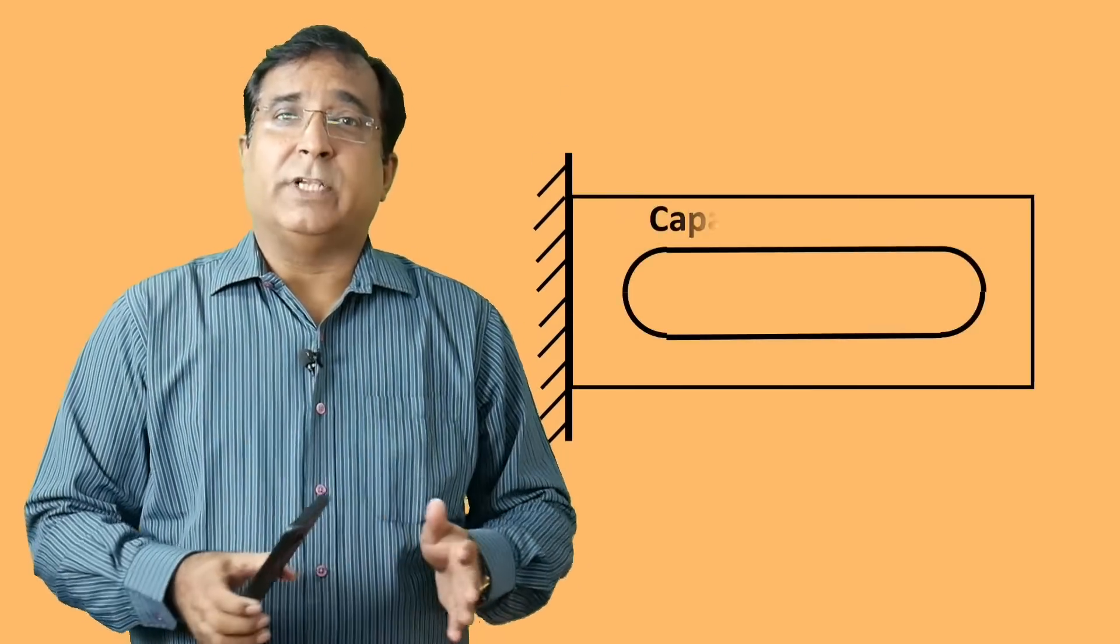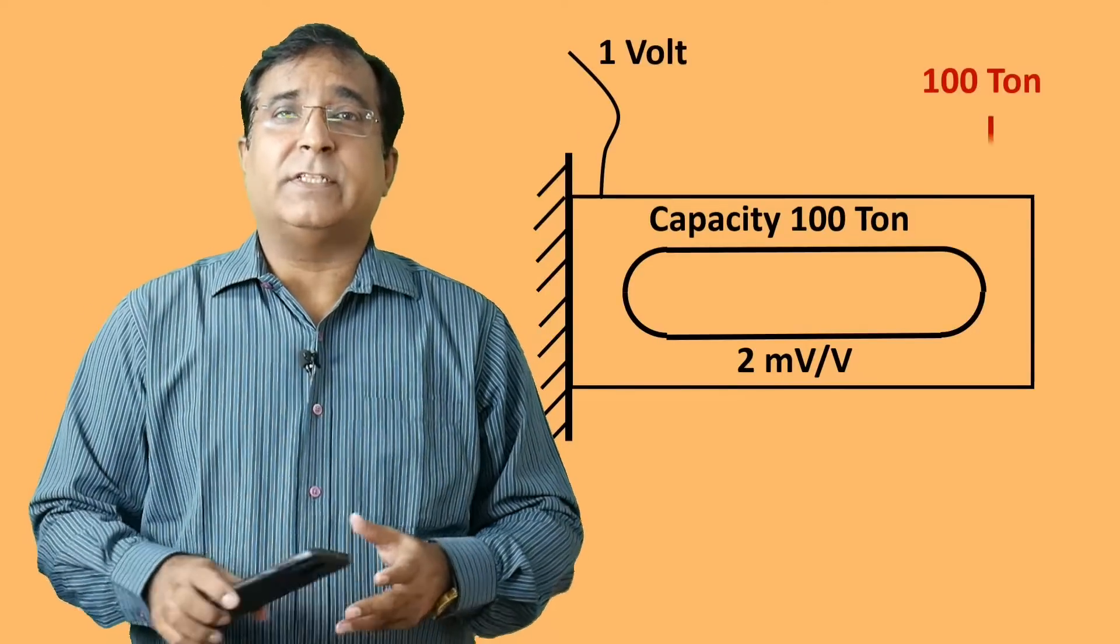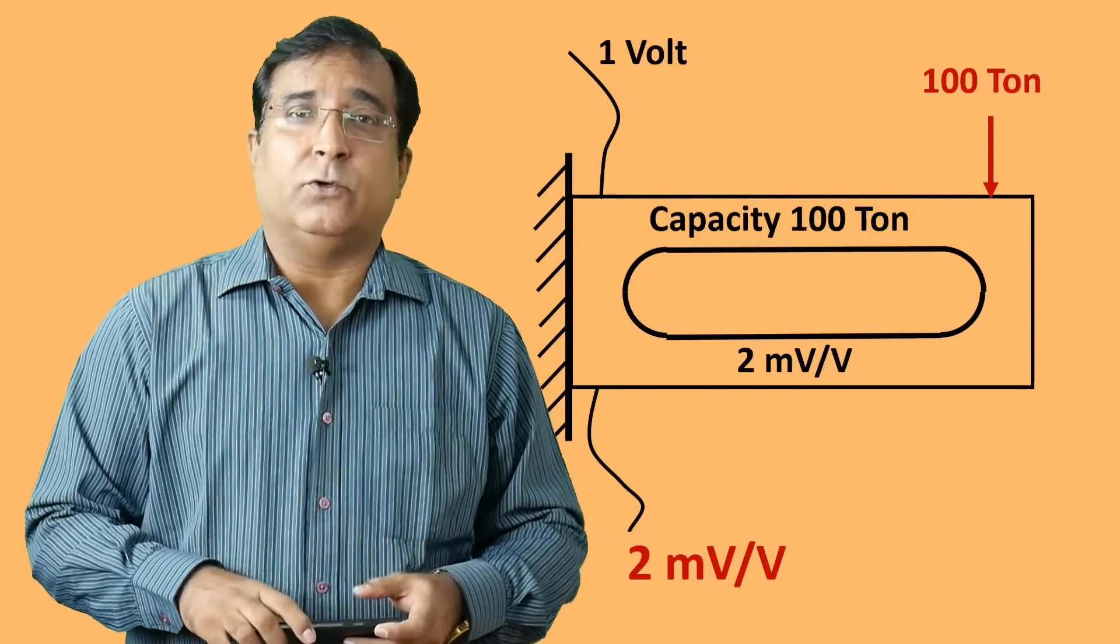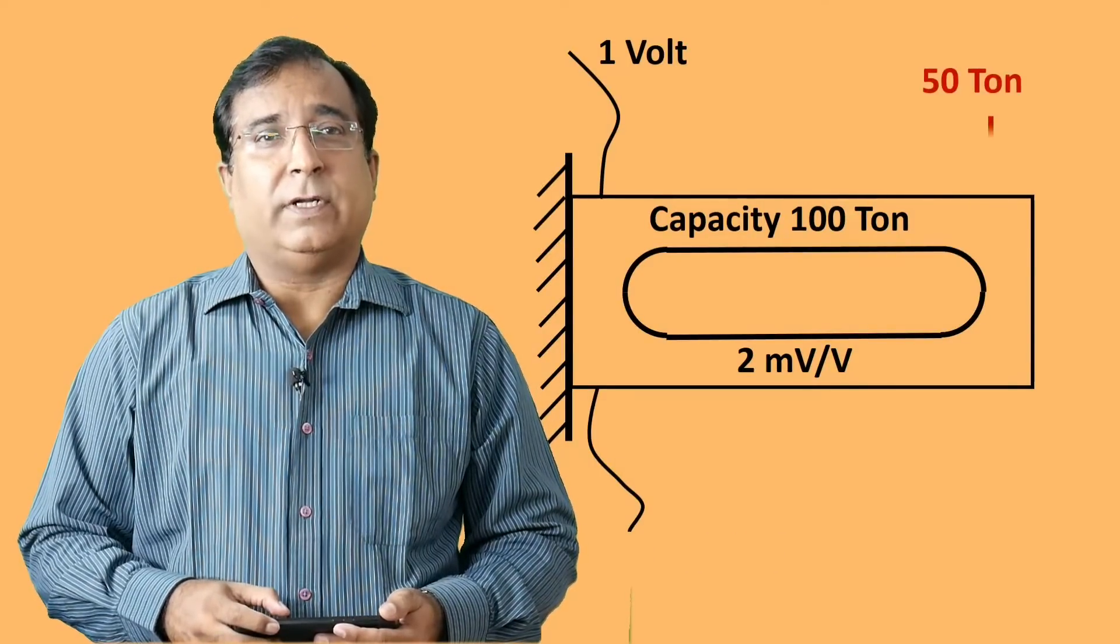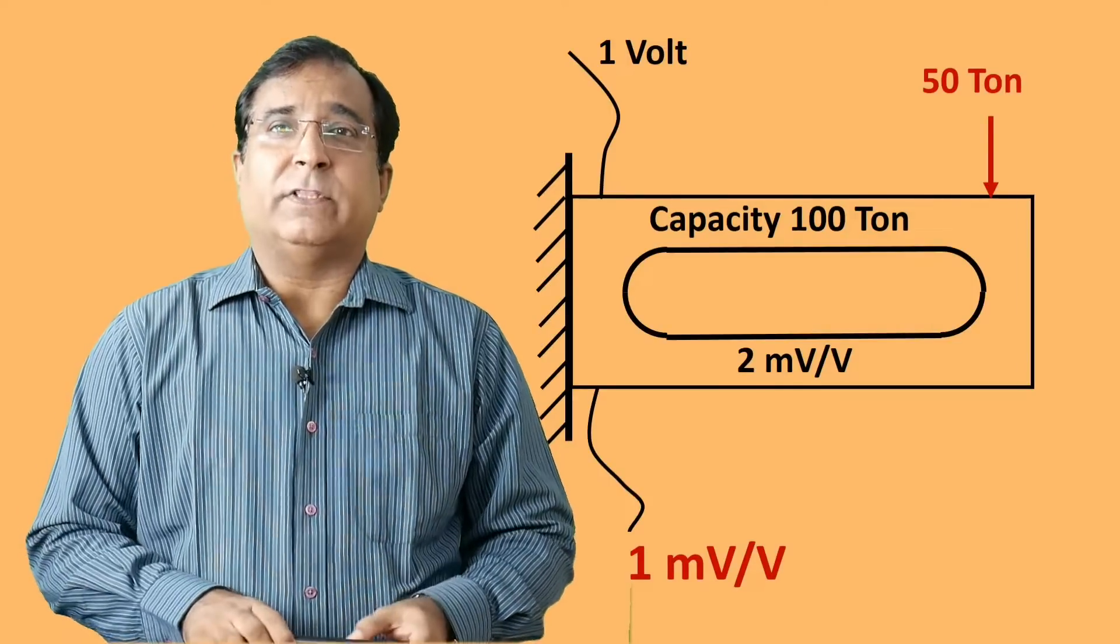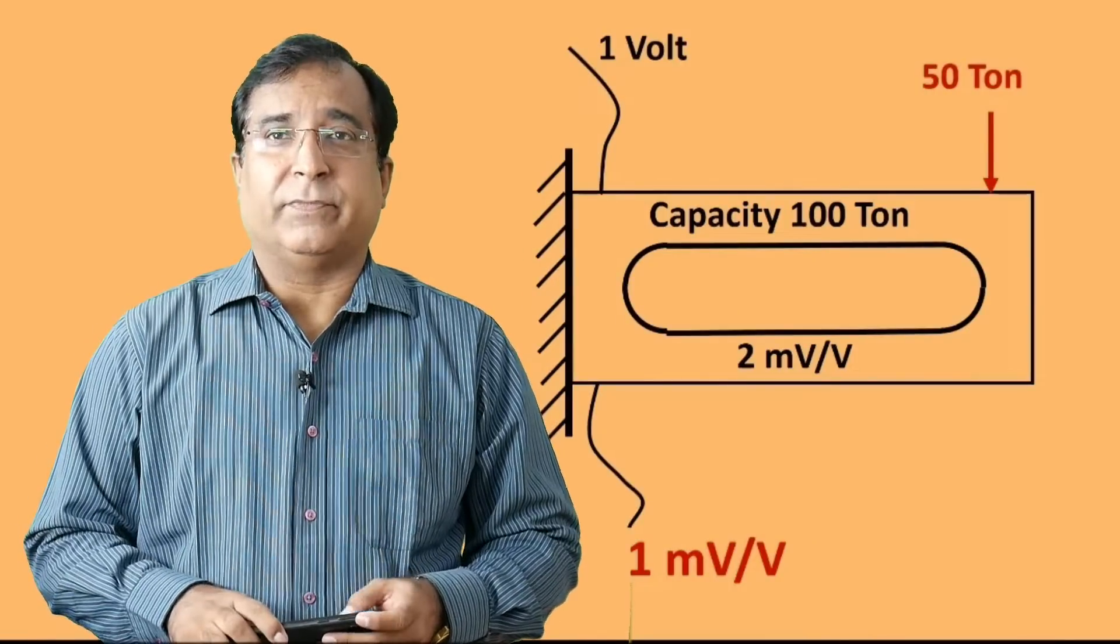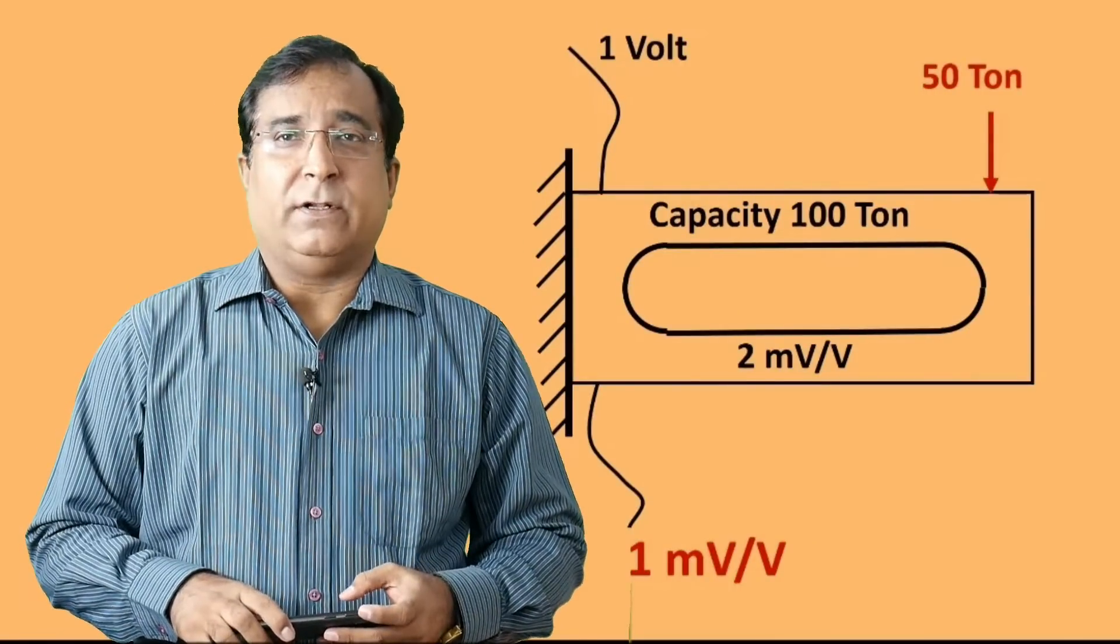Now suppose you have a load cell whose sensitivity is 2 millivolt per volt and capacity is 100 tons. If it is supplied with 1 volt excitation voltage, so at 100 tons 2 millivolt output will be from the load cell and if load is reduced to 50 ton then it will produce 1 millivolt at the output. Simple math. So by measuring this millivolt with a multimeter you can have a fair idea of what load it is sensing. So this funda will help you while troubleshooting of a load cell.